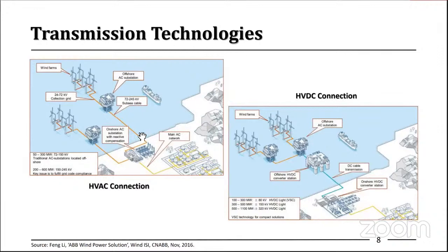A set of static filters and variable shunt reactors are also deployed at the LV side of the onshore transformer to reduce harmonics and ensure grid compliance. For example, in the UK, the metering point is at the LV side of the offshore substation. For Germany, it is at the HV side of the offshore substation, and in the US market, the metering point is at the LV side of the onshore substations.